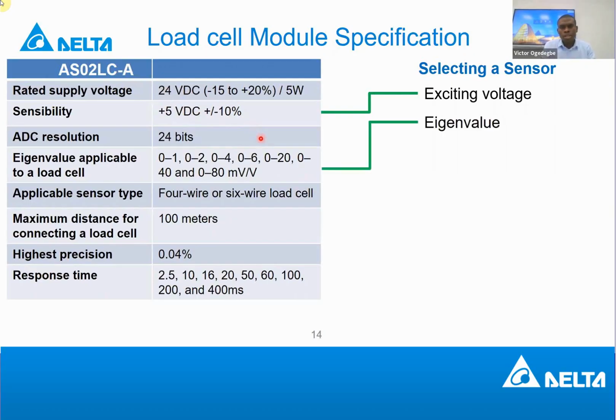Another thing that's also important to select a sensor is the Eigenvalue. This determines the characteristic output of the sensor. For this module, the Eigenvalue supported is from 0 up to 80. For example, if you have a very gigantic load sensor that is more than 80 millivolts, you can't use this module, because the Eigenvalue cannot meet the requirement. And do you know what will happen? If you use it, the reading will be wrong. So that's why this Eigenvalue is very important.